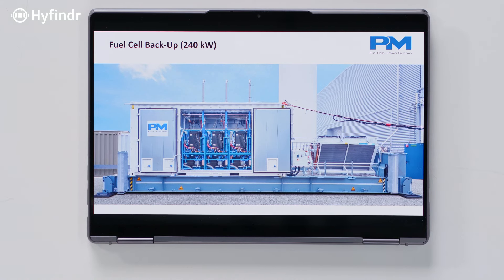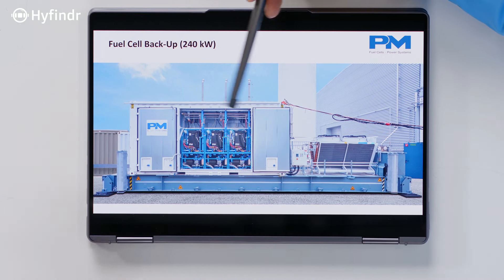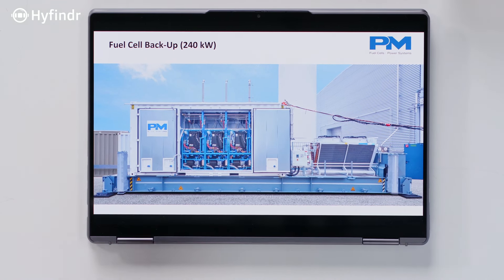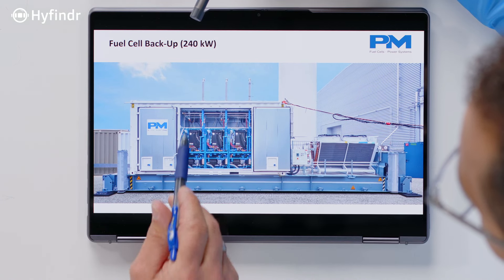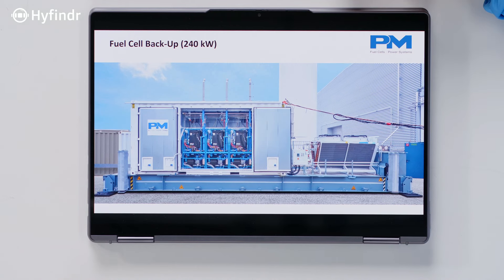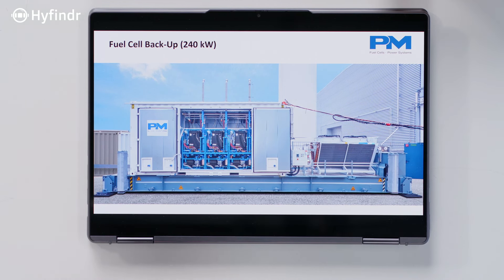This is a complete backup power system — a containerized solution. Everything from the previous slide — the battery, the fuel cell system, the DC-AC converters, the DC-DC converters, the cooler — everything is placed on one rack. There are three fuel cell systems — the stack is the black box inside each frame — these are our High Frame systems, and multiplied by three we come up to roughly 130 kilowatt of fuel cell power. The peak power of 240 kilowatt can be supplied by the battery and DC-AC converter, running for a couple of minutes, and then the fuel cell takes over and runs stable at 130 kilowatt or a lower load.